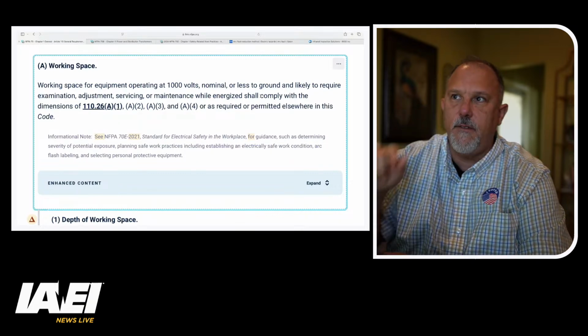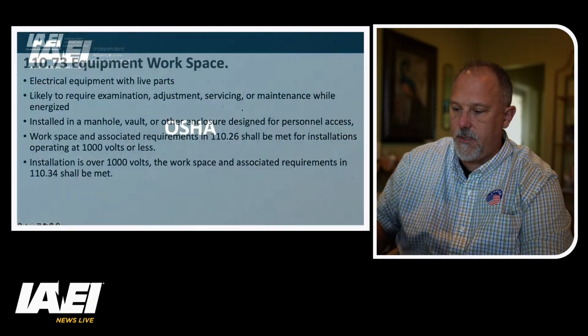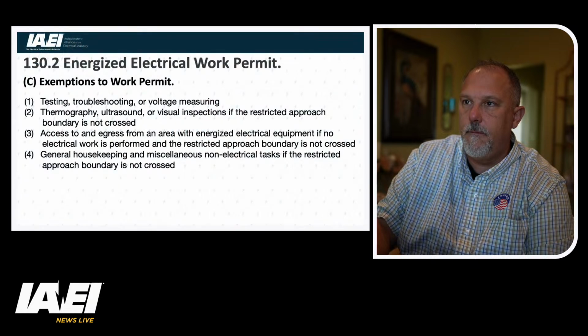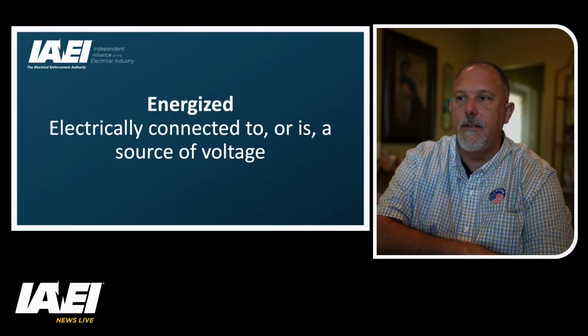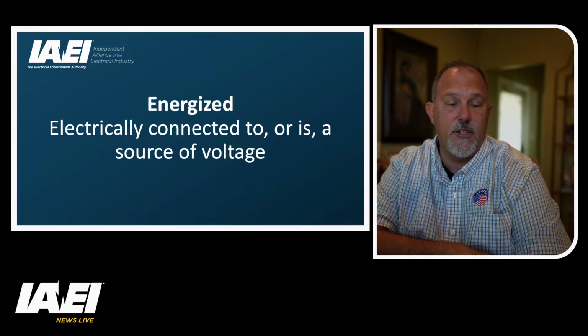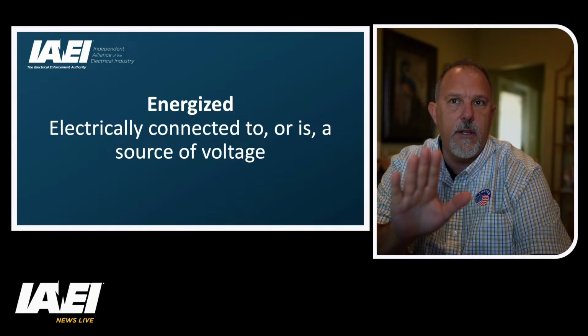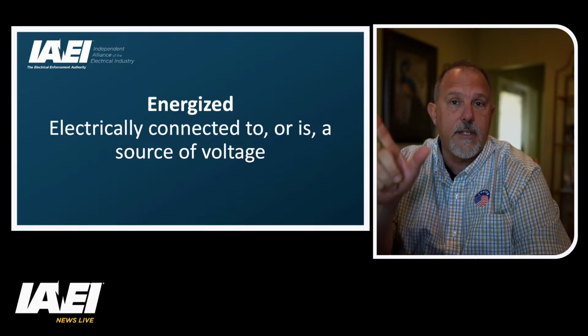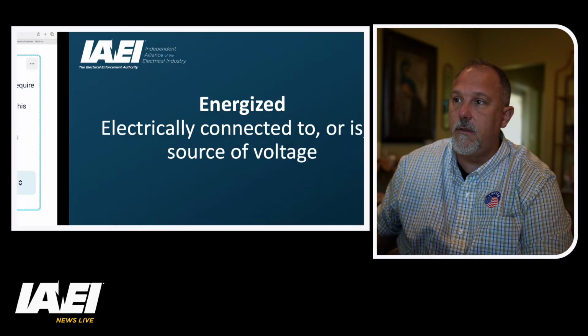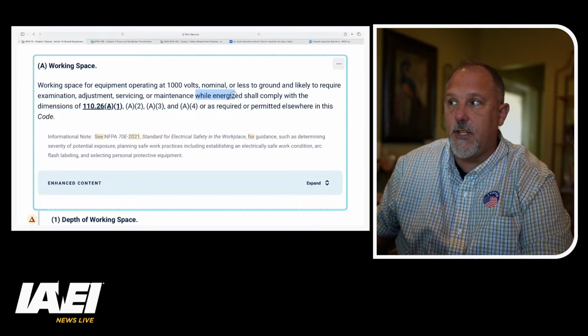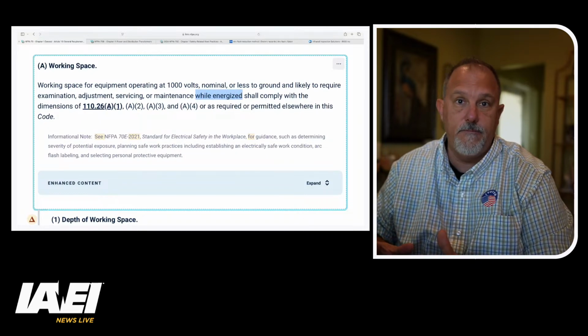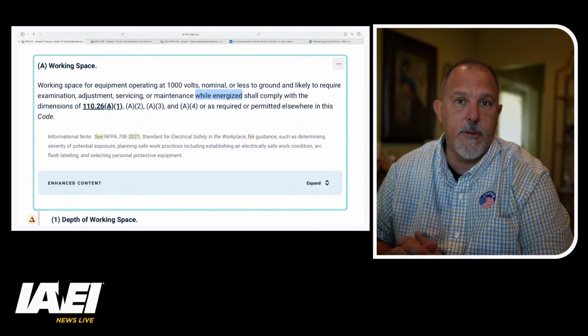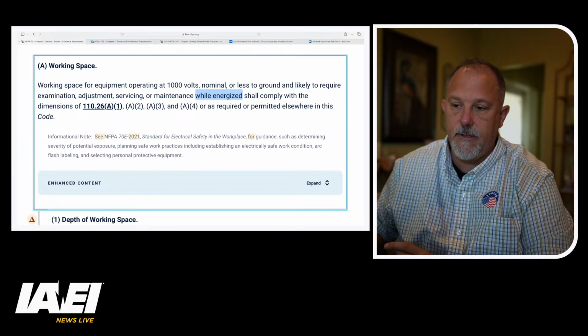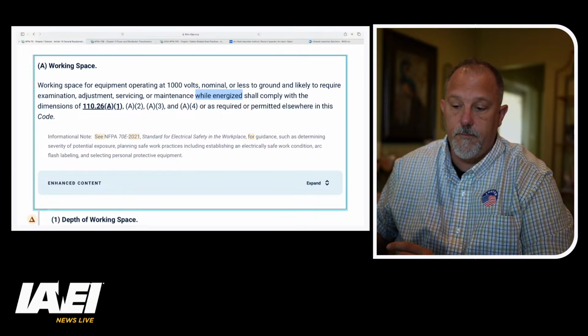And energized is a defined term, which we said was my first slide, electrically connected to a source of voltage. So I don't care if it's exposed or not exposed. That language requires it while energized, just while voltage is applied. It doesn't matter if it's barriered off, finger safe, or anything like that. That's not the way the language reads. So I think it's an important distinction to think about.